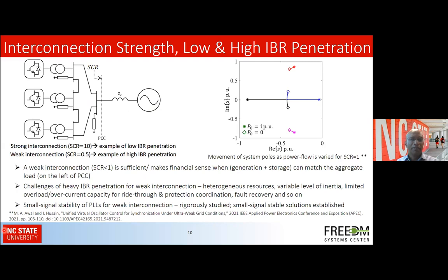So now, with heavy penetration, the challenges are that these IBR resources could be of heterogeneous types, with various levels of inertia. They have different types of overload capacity and ride through capability. And then also for a weak connection, the PLL becomes unstable. So this is very extensively, rigorously studied, and we all know the issues: with high penetration and weak interconnection, the PLL would cause a problem.